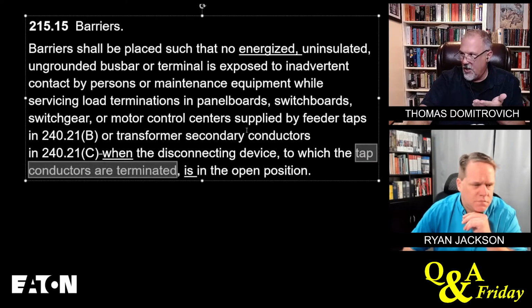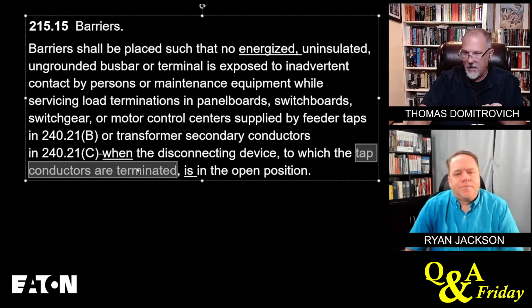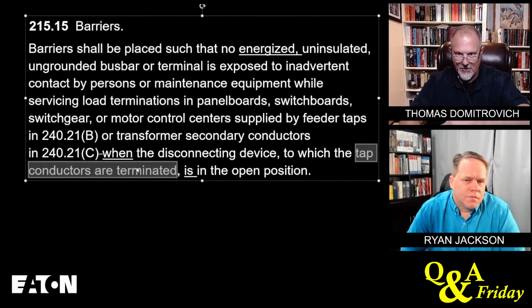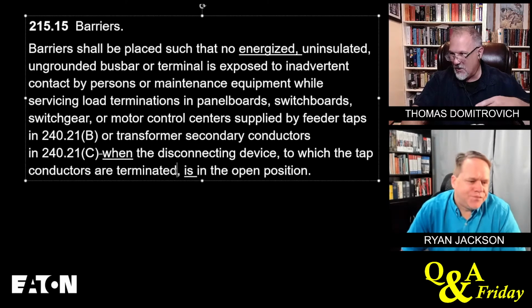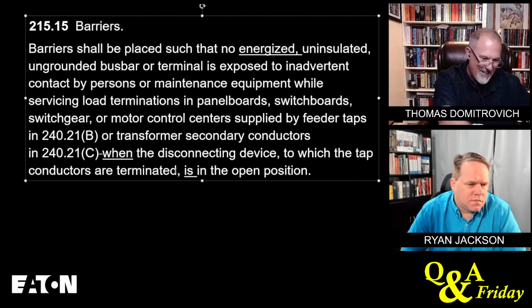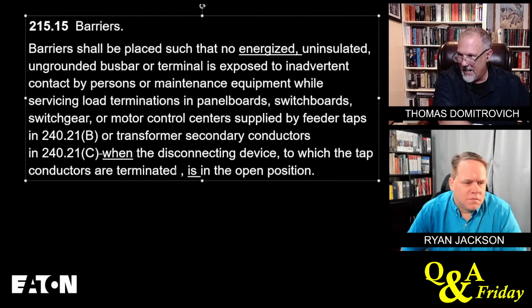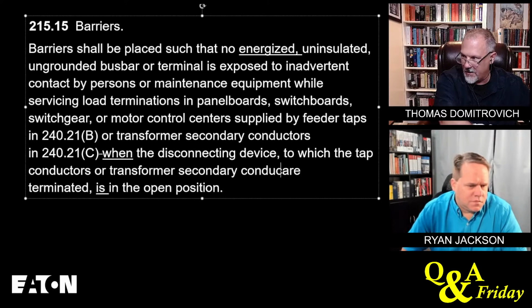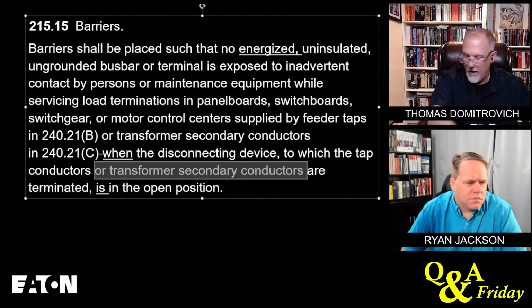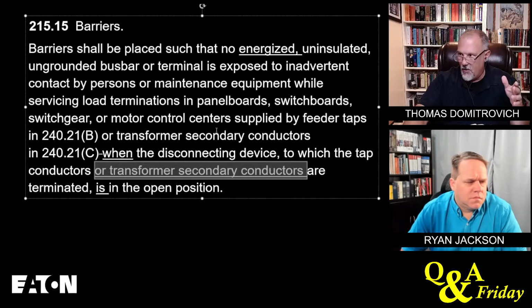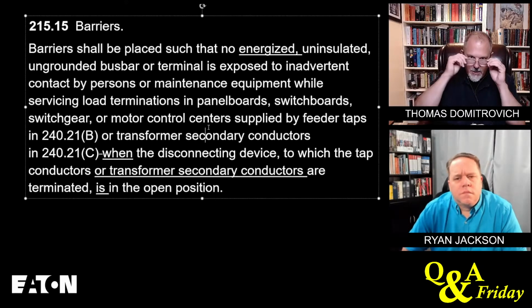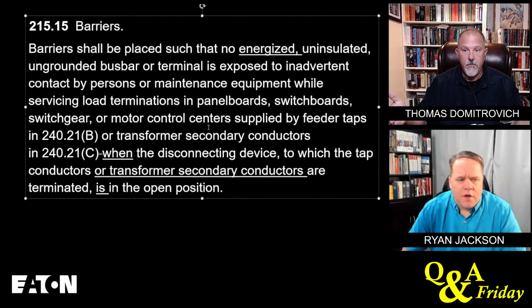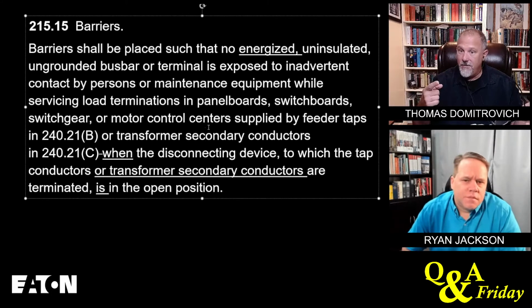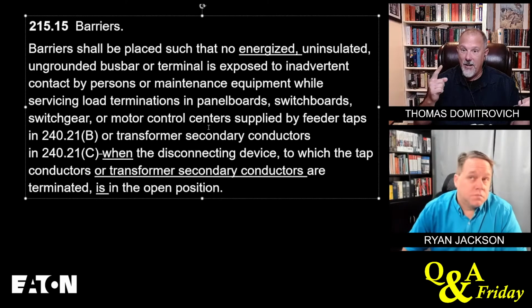Okay? And then it says when the disconnecting device to which the tap conductors are terminated. So I said, well, wait a second. We said to which the tap conductors are terminated. What about the transformer secondary conductors? So I had created language that I circulated to a few different people that said, to which the tap conductors or transformer secondary conductors are terminated. And so what I got back was, Tom, those conductors are tap conductors. Yeah, and I agree with that statement. But not all of them are. Fair enough.